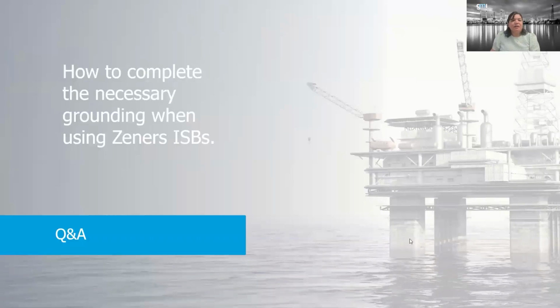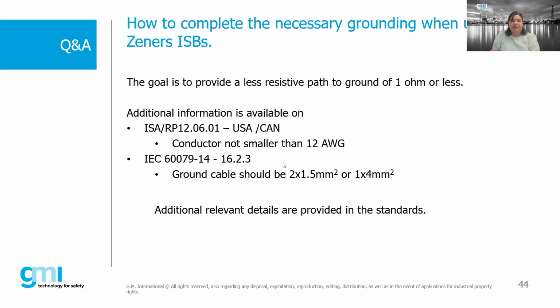Another question we got: how to complete the necessary grounding when using Zener barriers? I think Bob already covered that. One of the main things is less than 1 ohm resistance on your clean ground. For the United States and Canada, or whoever follows the NEC installation rules, that standard covers the requirements for grounding, and the gauge of the cable is important. For international, like Bob was saying, you could use 2 ground pads or 1, and there are also some rules about the gauge of that conductor to be utilized.